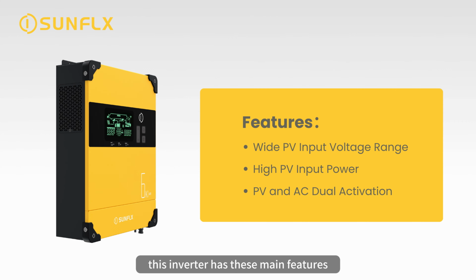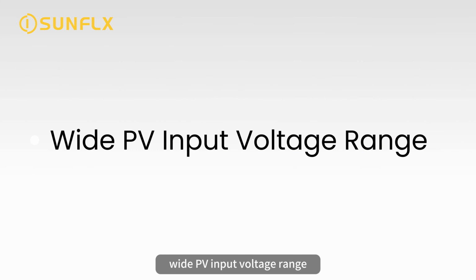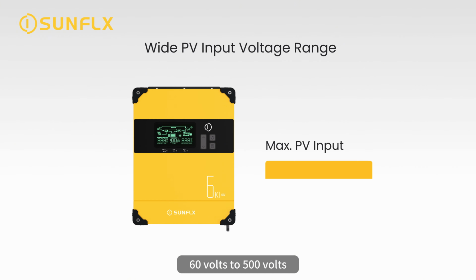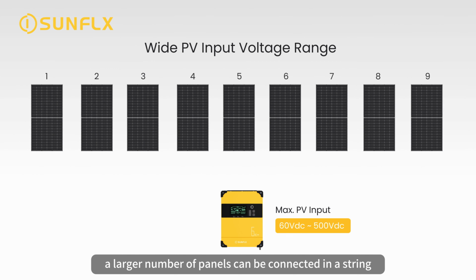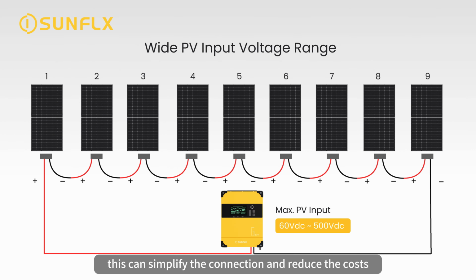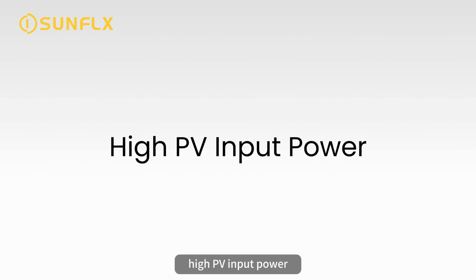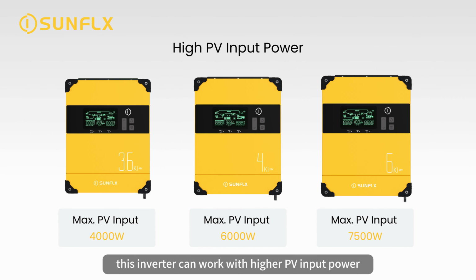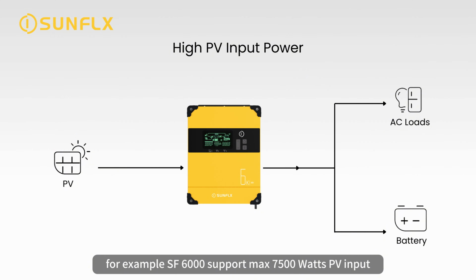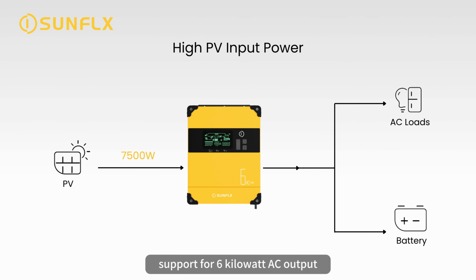This inverter has these main features. Wide PV input voltage range. With a PV input voltage ranging from 60 volts to 500 volts, a larger number of panels can be connected in a string. This can simplify the connection and reduce the costs. High PV input power. This inverter can work with higher PV input power. For example, SF 6000 support, max 7500 watts PV input, which means while the PV power support for 6 kilowatt AC output, there is still extra 1.5 kilowatt PV power can be charged to the battery. So this inverter enables your battery be charged on time and always ready for a power outage.